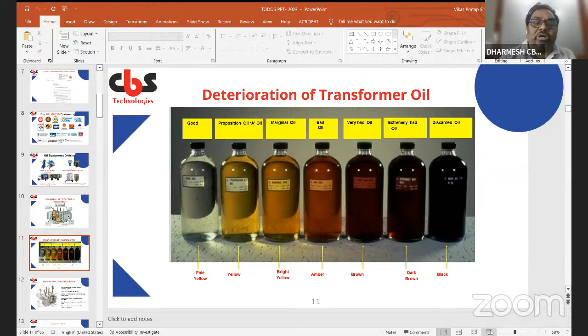Well, this is the most critical asset. Transformer is the most critical asset in power utilities. The life expectancy of a transformer is about 25 years, but this can be extended with more things. If we add good things there, like online moisture monitoring, proper maintenance, and proactive maintenance, the life expectancy of the transformer will be extended up to 40 years.